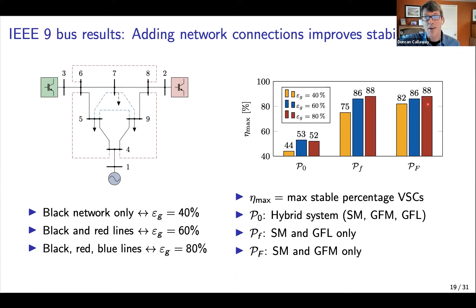So for question two: do conventional power systems analysis modeling assumptions hold in low inertia grids? The answer is that transmission line models matter a lot, and in some cases in quite fundamental ways. You might mischaracterize the point at which instability arises, or even more extremely, conclude a system could never be stable—as we found with the dynamic-less transmission lines—versus a system that can be stable over a broad range of operating conditions. This is for the specific case of the 100% power electronic converter grid.